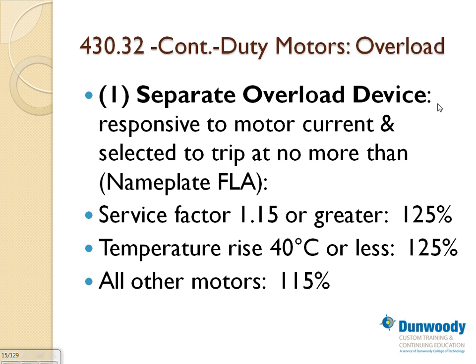Protection number 1 is a fuse and circuit breaker. That's the upper level for short circuit and ground fault. You have a fuse or circuit breaker. Then you go down to protect it from single phasing or from being overloaded. You put a tiny little device, electronic or a heater, that protects the motor from overload.